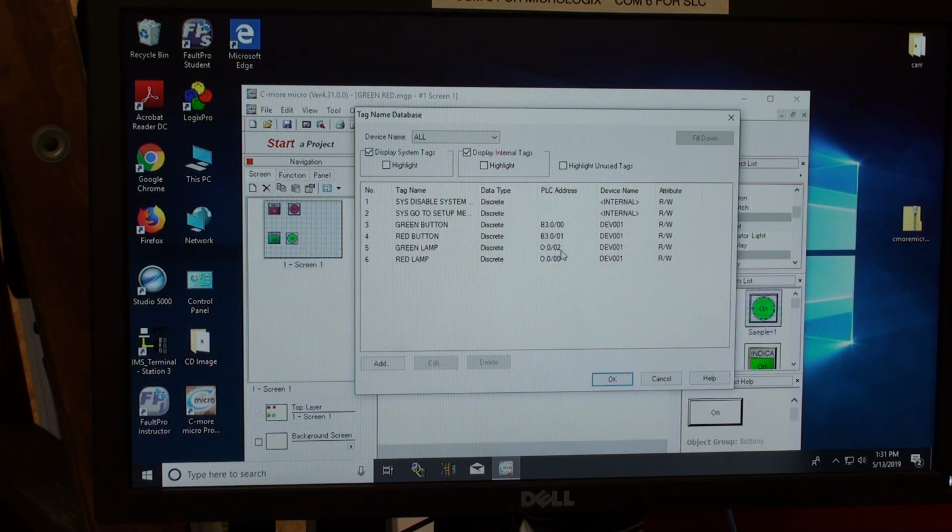And the output we're turning on is a real world output. It's really the light on a traffic light, but the HMI is going to tell us that too. It's going to light up to indicate it knows that output is on right here. So we get to see a couple of things. Maybe we've got our back to whatever it is that's operating we can't see. So if we had an HMI panel, we know at least we're sending a signal for it to be on. Now just like if my bulb would burn out, my HMI would still come on, but my bulb wouldn't come on. So we could still have some differences, but we know when it should be on.